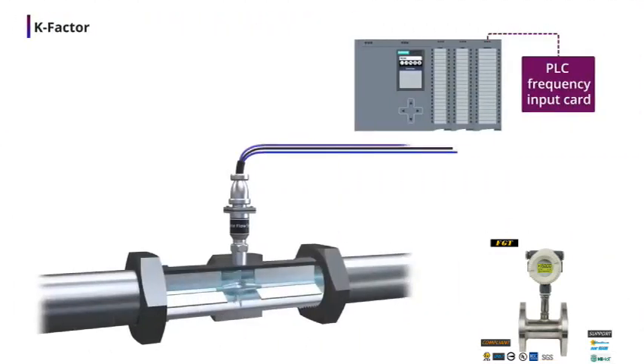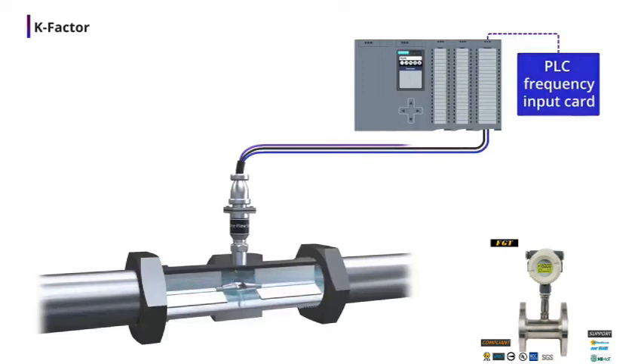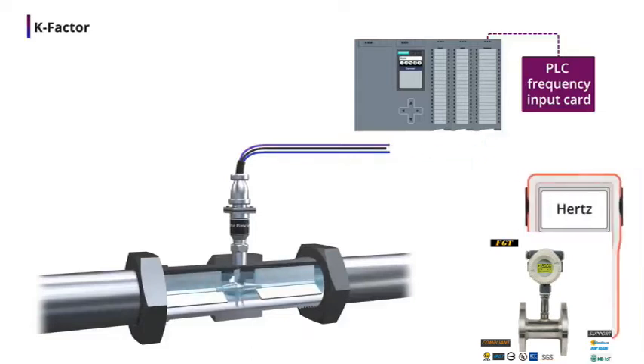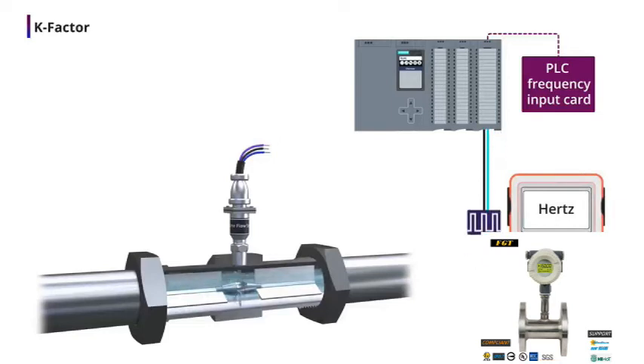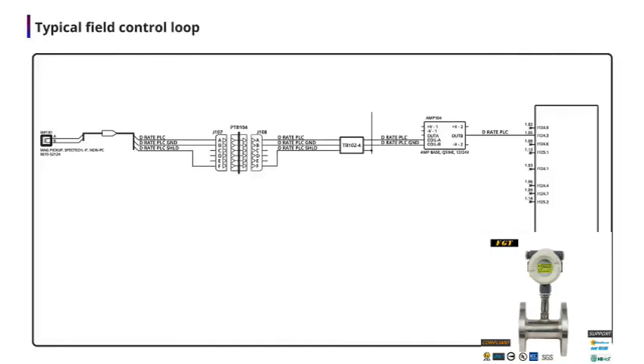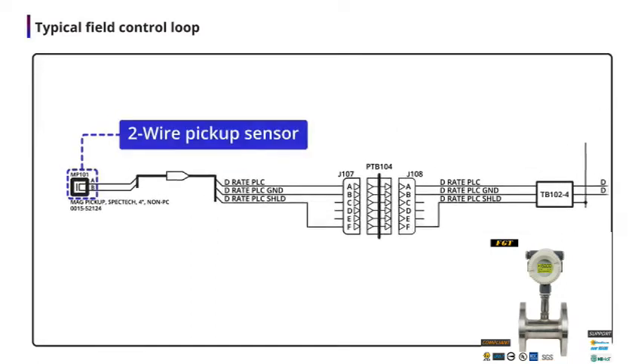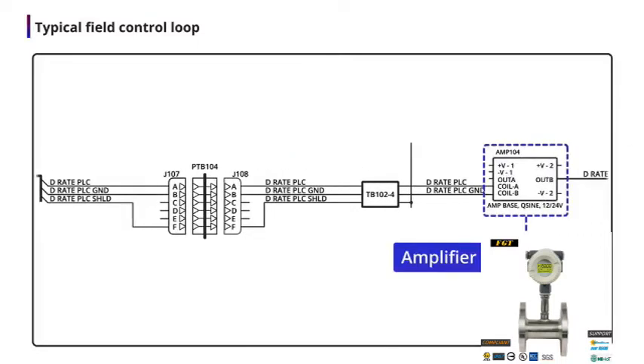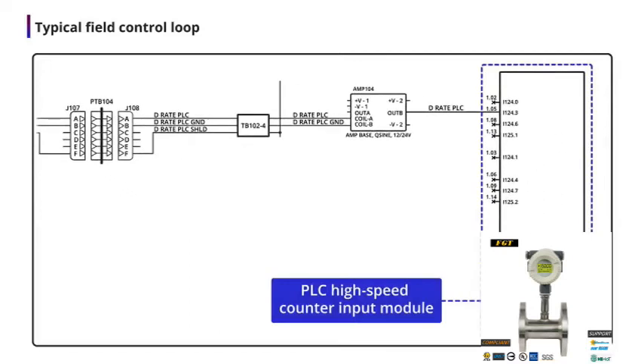We can connect the turbine flow meter to a PLC frequency input card. The input frequency now represents the volumetric flow rate. If we are troubleshooting or performing loop calibration, we can use a calibrator with a variable frequency output to simulate the turbine flow meter. Here's an example of a turbine volumetric flow rate measurement loop. A 2-wire passive sensor pickup unit produces AC-like pulses, which are conditioned by an amplifier, before being sent to a high-speed counter PLC input module.